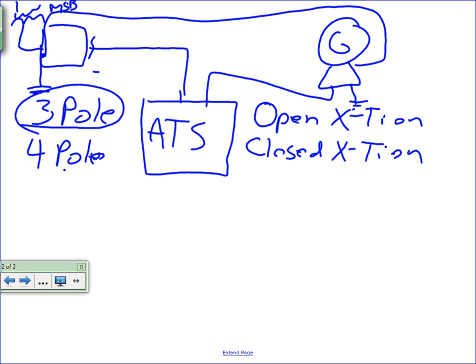Okay. And it's up to the engineer. I've seen them go both ways, where they bond this or they bring it back to here. Even the generator guys aren't always sure when they use a 3- or a 4-pole transfer switch. It gets kind of confusing, but that's the difference. If you know they're going to bond that generator as a service entrance, then you have to use a 4-pole breaker or transfer switch.